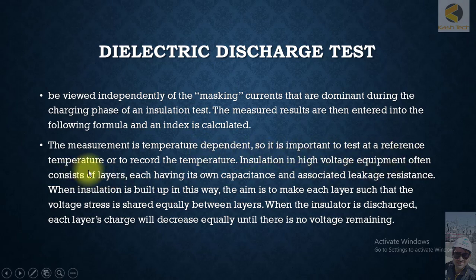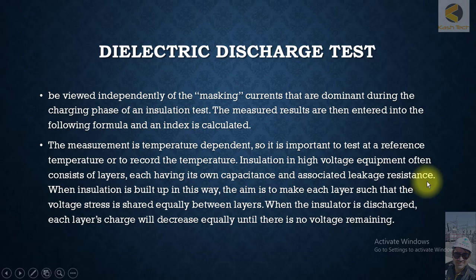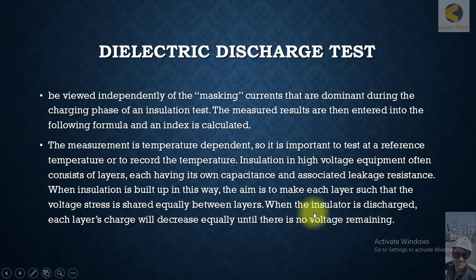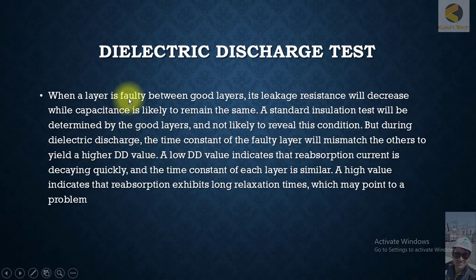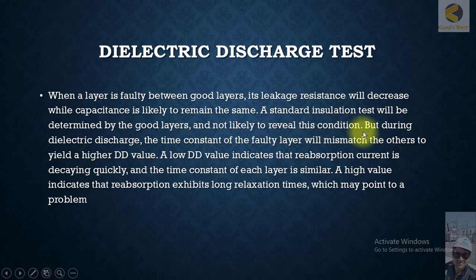The measurement is temperature dependent, so it's important to test at a reference temperature or to record the temperature. Insulation in high voltage equipment often consists of layers, each having its own capacitance and associated leakage resistance. When insulation is built up in this way, the aim is to make each layer share the voltage stress equally between layers. When the insulator is discharged, each layer's charge will decrease equally until there is no voltage remaining. When a layer is faulty between good layers, its leakage resistance will decrease while capacitance is likely to remain the same.